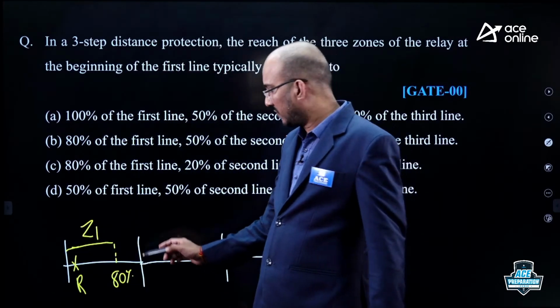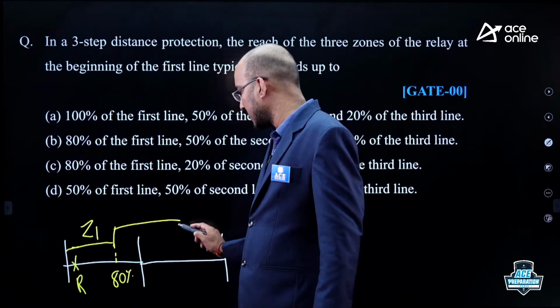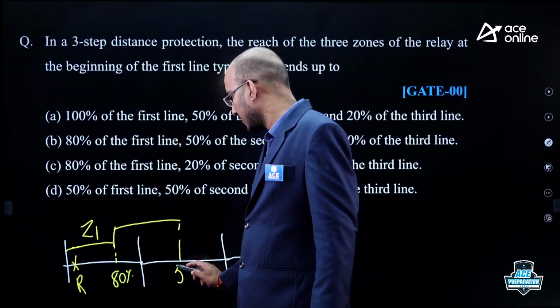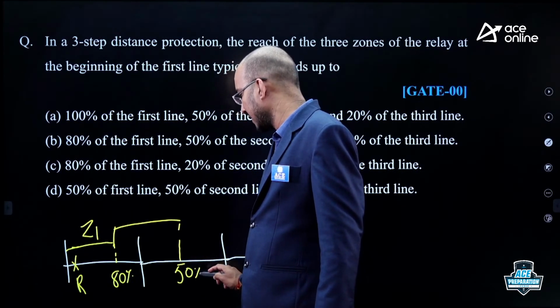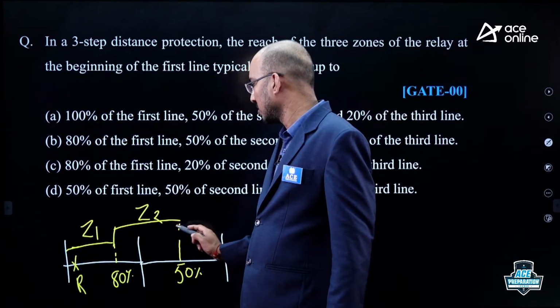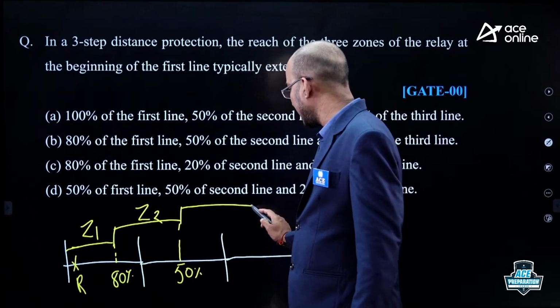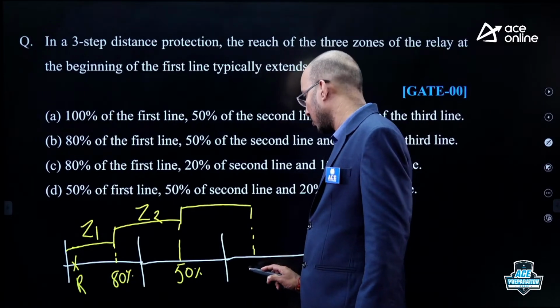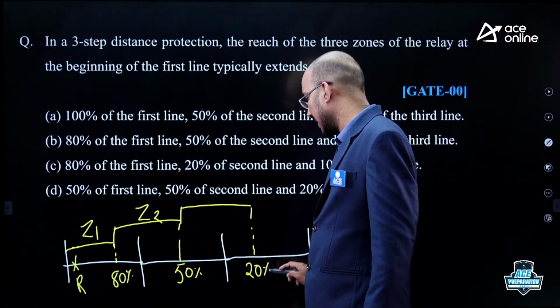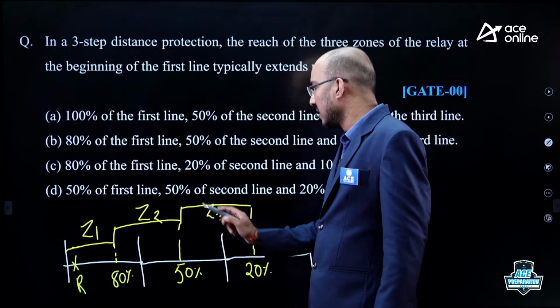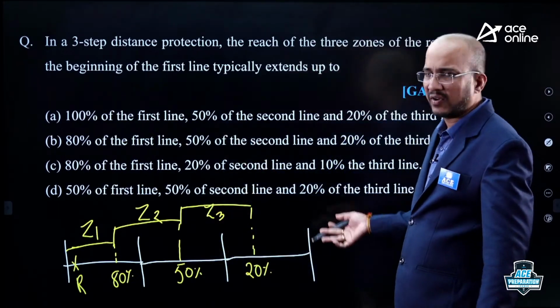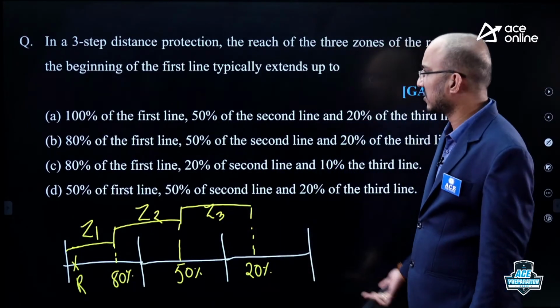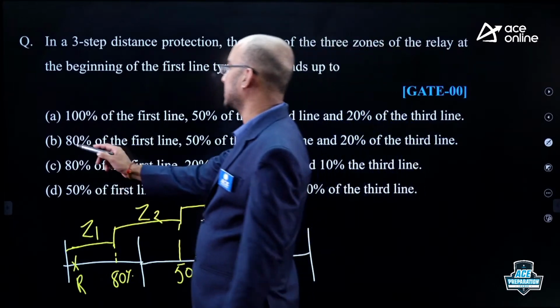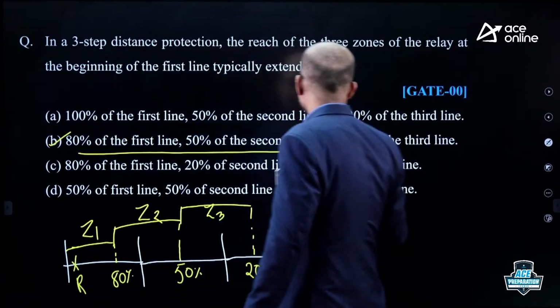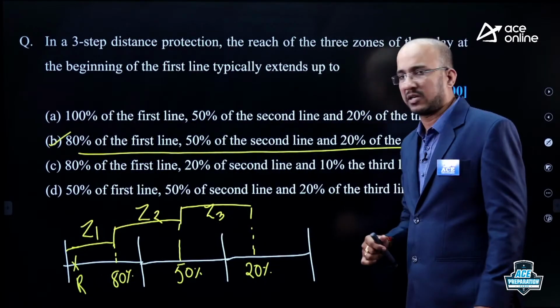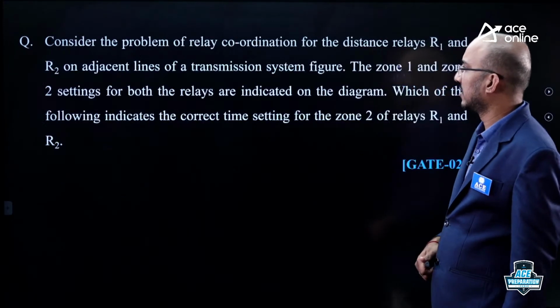Zone 2 will be extended up to 50% of the second line. This comes under zone 2, and zone 3 is extended up to 20% of the third line. This is zone 3. So look at the options. This we will regularly discuss in class. Okay, 80% of the first line, 50% of the second line, and 20% of the third line.